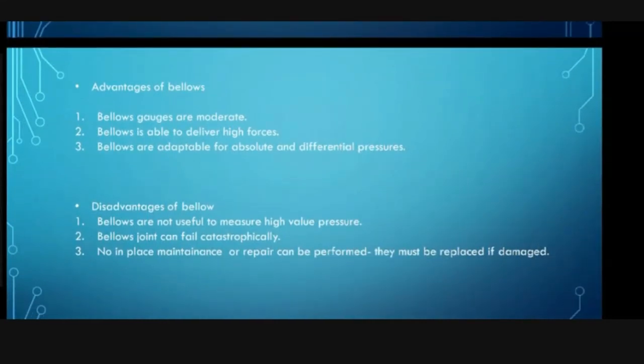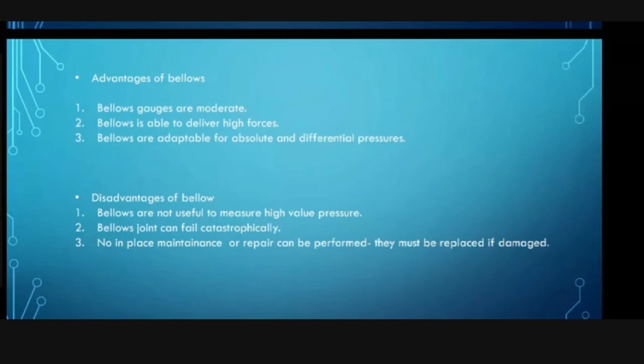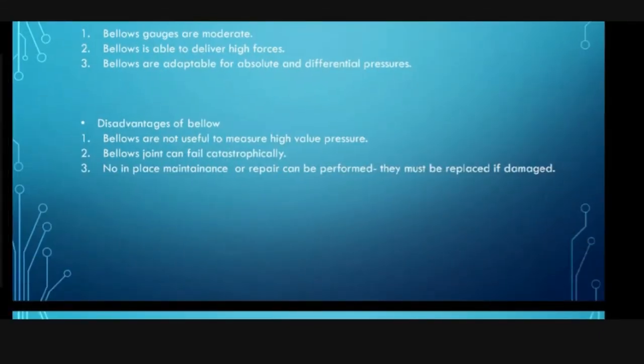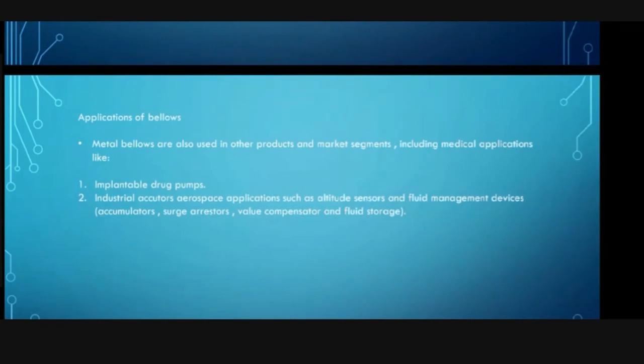Advantages of bellows. Bellows gauges are moderately priced. Bellows are able to deliver high forces. Bellows are adaptable for absolute and differential pressures. Disadvantages of bellows. Bellows are not useful to measure high value pressure. A bellows joint can fail catastrophically. No in-place maintenance or repair can be performed. They must be replaced if damaged. Application of bellows. Metal bellows are also used in other products and market segments, including medical applications like implantable drug pumps, industrial actuators, aerospace applications such as altitude sensors and fluid management devices, accumulators, surge arresters, valve compensators, and fluid storage.